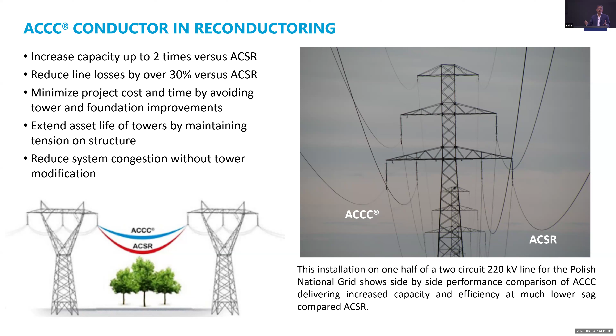And because it's got more aluminum in it, it is also much more efficient. This is an example from Malaysia. This is a connection line between Malaysia and Singapore. The TNB wanted to upgrade this line from 600 MVA to 1000 MVA. That's a 67% increase there. And they wanted to reuse the existing steel structure.